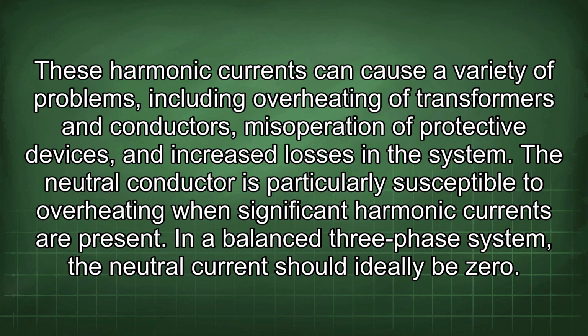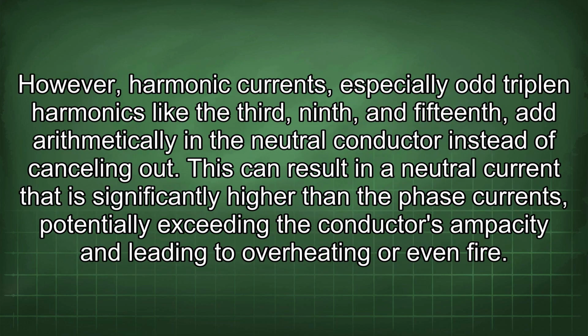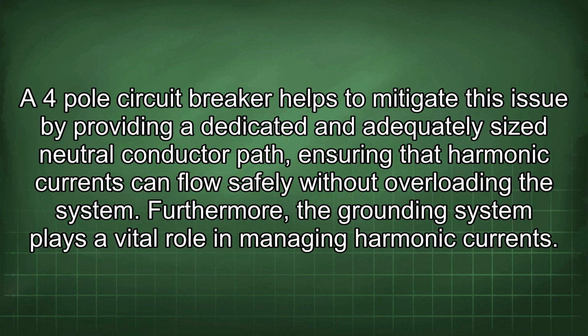The neutral conductor is particularly susceptible to overheating when significant harmonic currents are present. In a balanced 3-phase system, the neutral current should ideally be 0. However, harmonic currents, especially odd triplen harmonics like the 3rd, 9th, and 15th, add arithmetically in the neutral conductor instead of cancelling out. This can result in a neutral current that is significantly higher than the phase currents, potentially exceeding the conductor's ampacity and leading to overheating or even fire. A 4-pole circuit breaker helps to mitigate this issue by providing a dedicated and adequately sized neutral conductor path, ensuring that harmonic currents can flow safely without overloading the system.